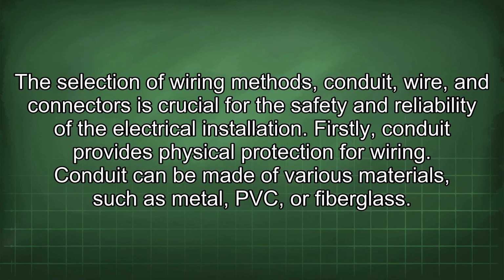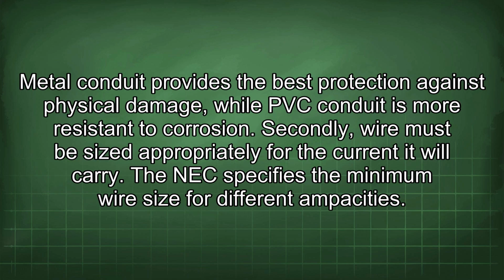The selection of wiring methods, conduit, wire, and connectors is crucial for the safety and reliability of the electrical installation. Firstly, conduit provides physical protection for wiring. Conduit can be made of various materials such as metal, PVC, or fiberglass. Metal conduit provides the best protection against physical damage, while PVC conduit is more resistant to corrosion.